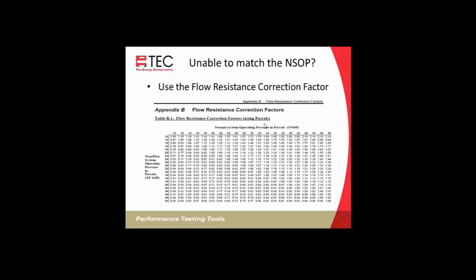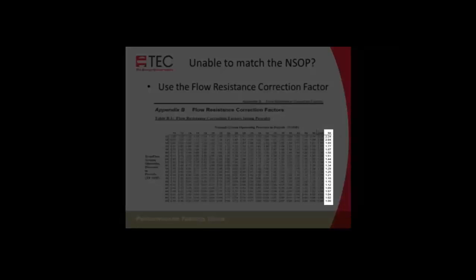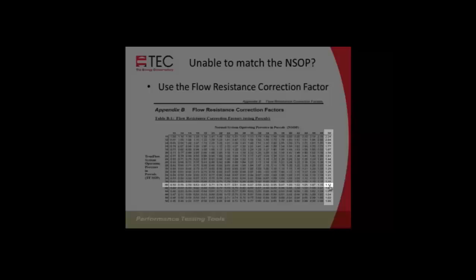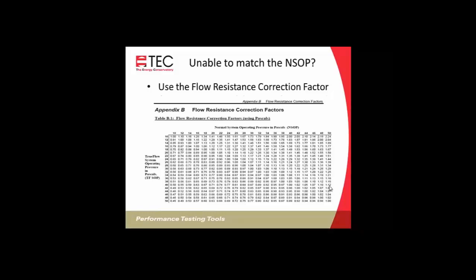So if you have a Duct Blaster and not a True Flow, you can go on our website and download that True Flow Manual. It's a free download, so you can get at this Appendix B for the flow resistance correction factors. And so let's say that your normal system operating pressure was 50, and you've got the Duct Blaster cranked all the way up. You're only able to get it to 40. You'll follow 40 across to 50 and find your correction factor of 1.12, and you'll use that for your correction factor.